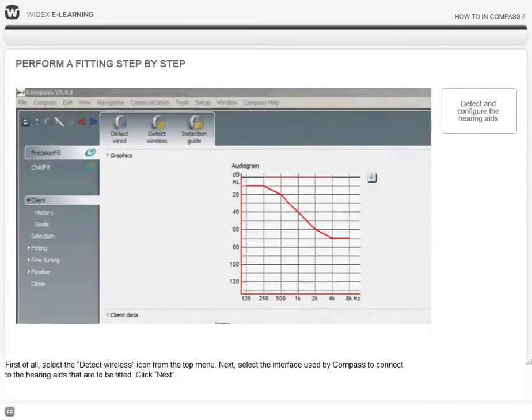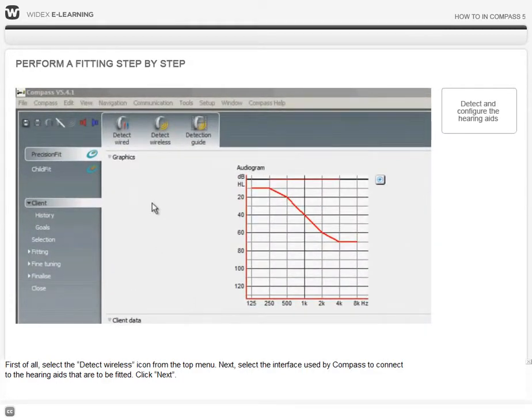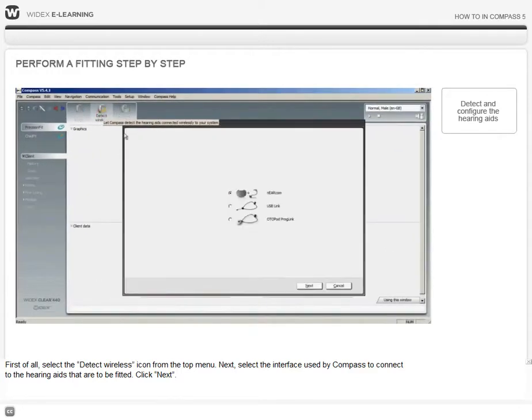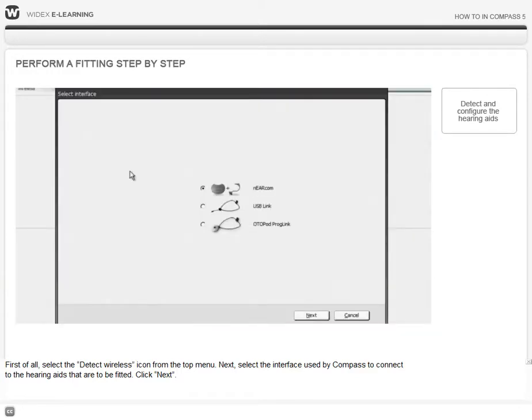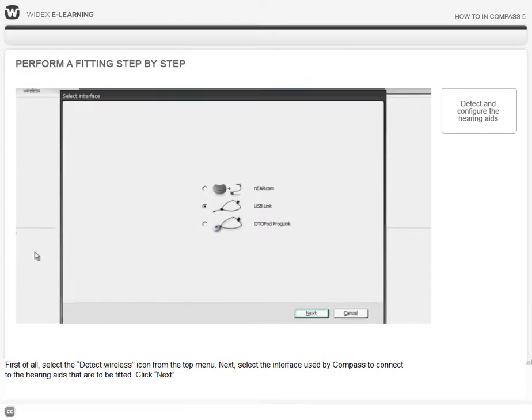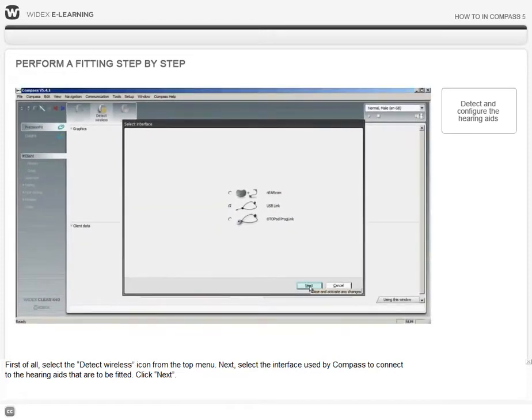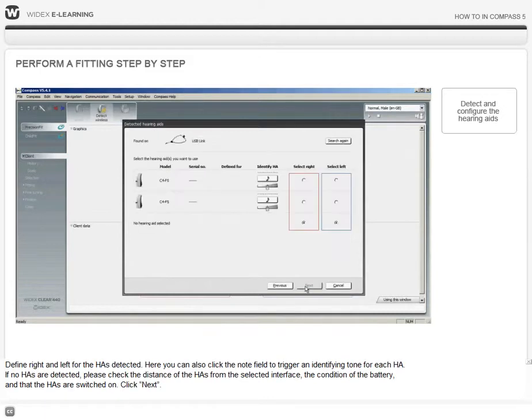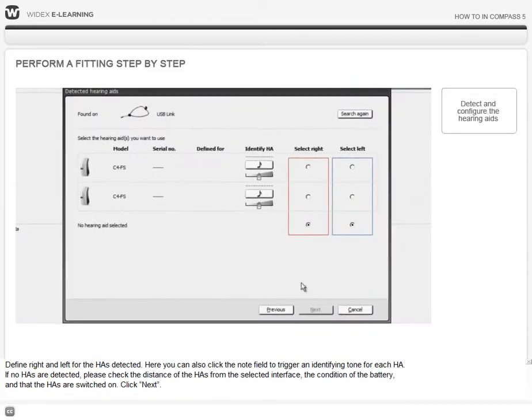First of all, select the Detect Wireless icon from the top menu. Next, select the interface used by Compass to connect to the hearing aids that are to be fitted. Click Next. Define right and left for the hearing aids detected. Here you can also click on the note field to trigger an identifying tone for each hearing aid. If no hearing aids are detected, please check the distance of the hearing aids from the selected interface, the condition of the battery, and that the hearing aids are switched on.